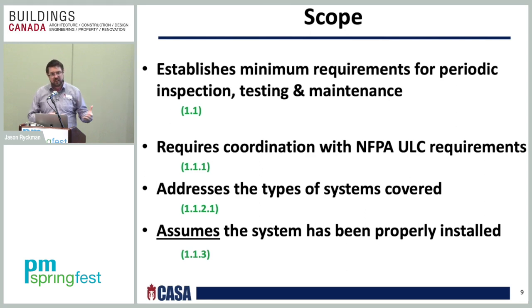Basically, with any standard, there's the scope and purpose. That is very important information that you have to understand whenever you're looking at an NFPA standard. The scope of NFPA 25 covers the administrative requirements for the periodic inspection, testing, and maintenance of water-based fire protection systems. In addition to the scope and purpose of the standard, Chapter 1 provides guidance throughout the document. You have to note as well that the most important point when using NFPA 25 is that the purpose of the standard is to verify operational status of the system.